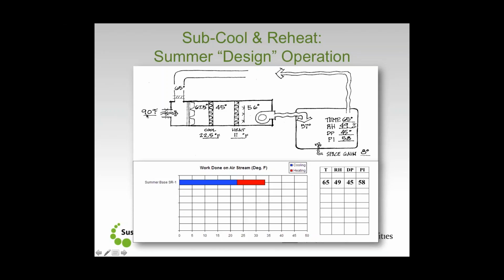And in order to do that on a 90-degree day, here's the process. We're going to have to cool that mixed air condition by 22.5 degrees, reheat it up by 11 degrees in order to get the right supply air condition going into the space. And here are the numbers that we wind up with, right? This is how much energy we use for cooling and heating in order to achieve that. Total in this scenario of about 33 degrees worth of work, give or take.